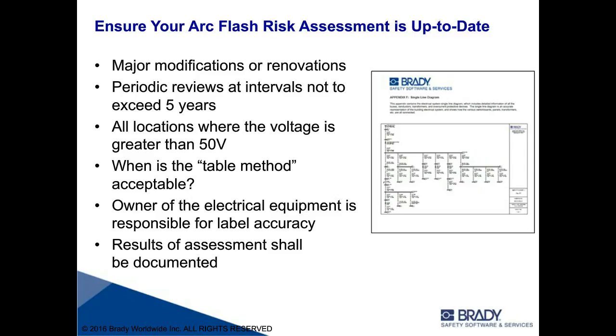But over the course of time, facilities make a lot of little changes. So what the code defines is that you have to update, or essentially audit, your arc flash risk assessment at intervals not to exceed 5 years. Over the course of those 5 years, you might move a piece of equipment to the other side of the room. You might add 1 or 2 pieces of equipment. You might delete a couple of pieces.